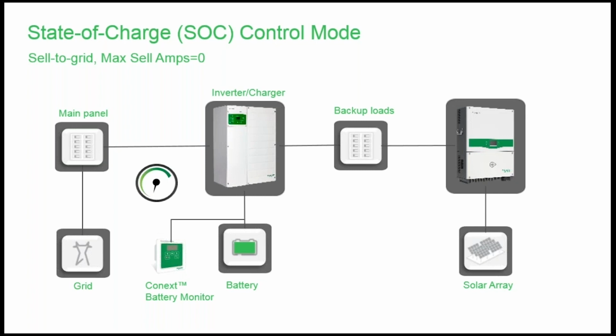Does anybody remember the Trace SW? It had an LBX mode. That meant low battery transfer. That feature allowed customers to remain connected to the grid, but draw virtually nothing from the grid. But they didn't have state of charge control back then. This was accomplished by opening the grid transfer relay. The XW Pro can actually stay connected to the grid and draw virtually 0 to support the load by enabling sell mode and setting the max sell amps to 0.